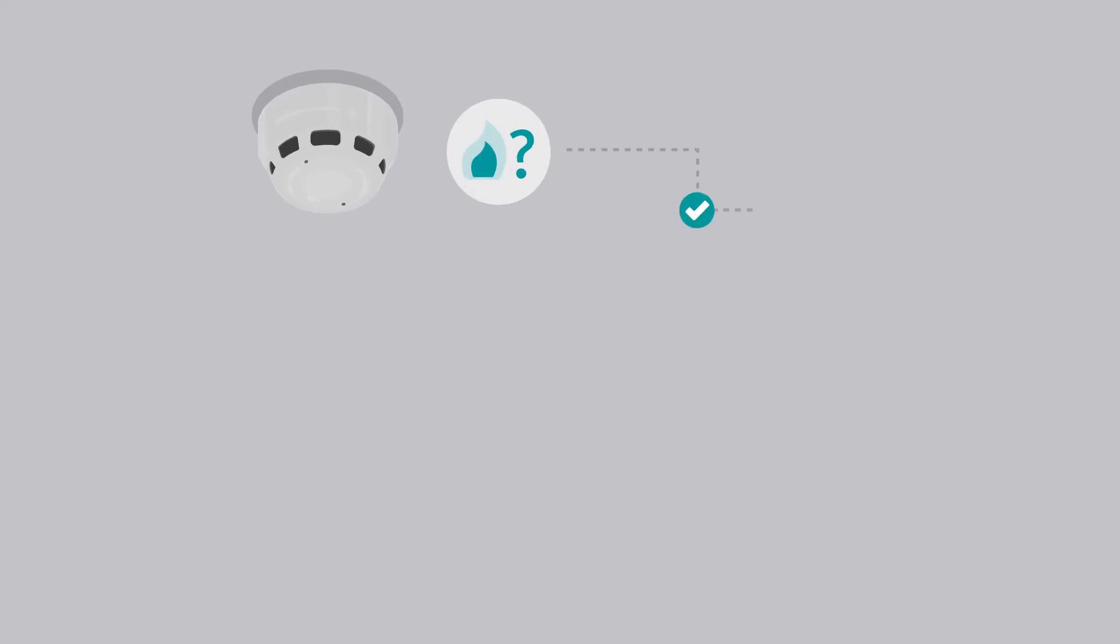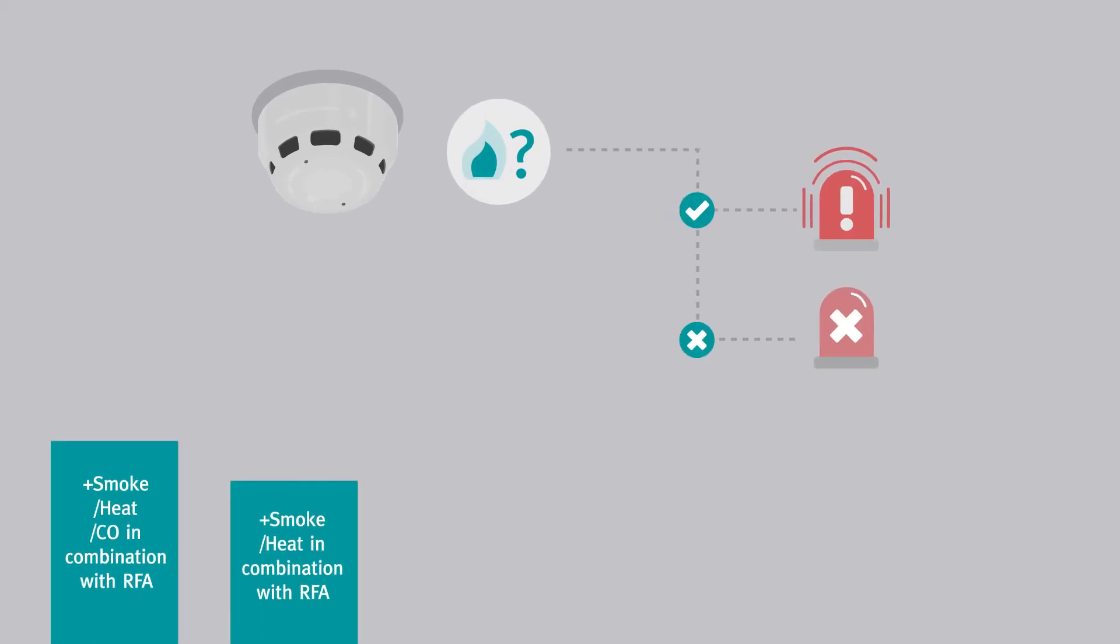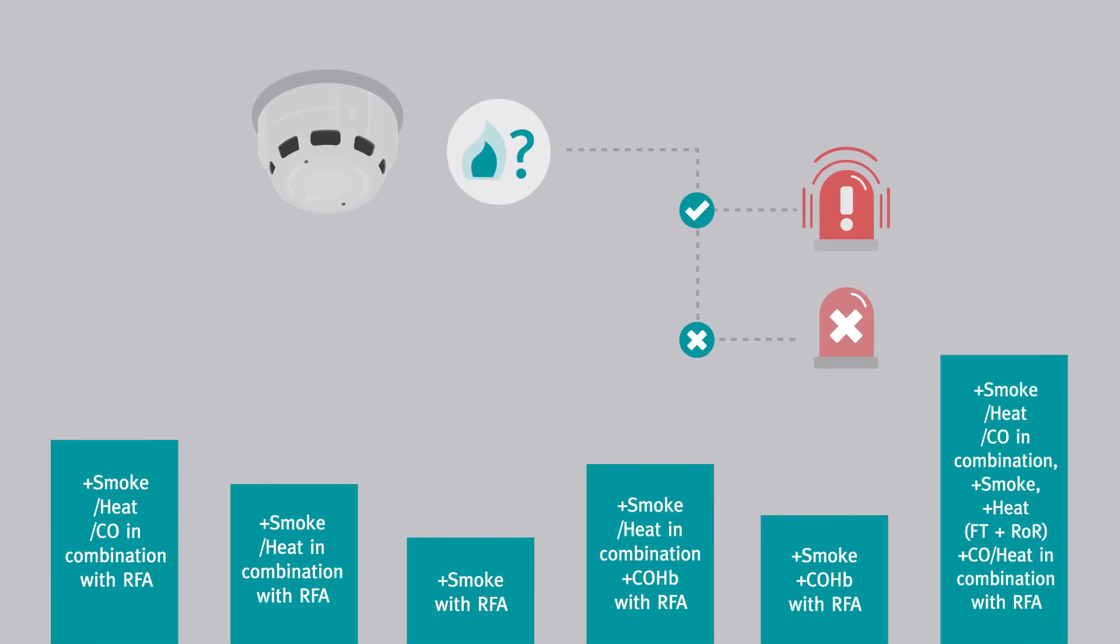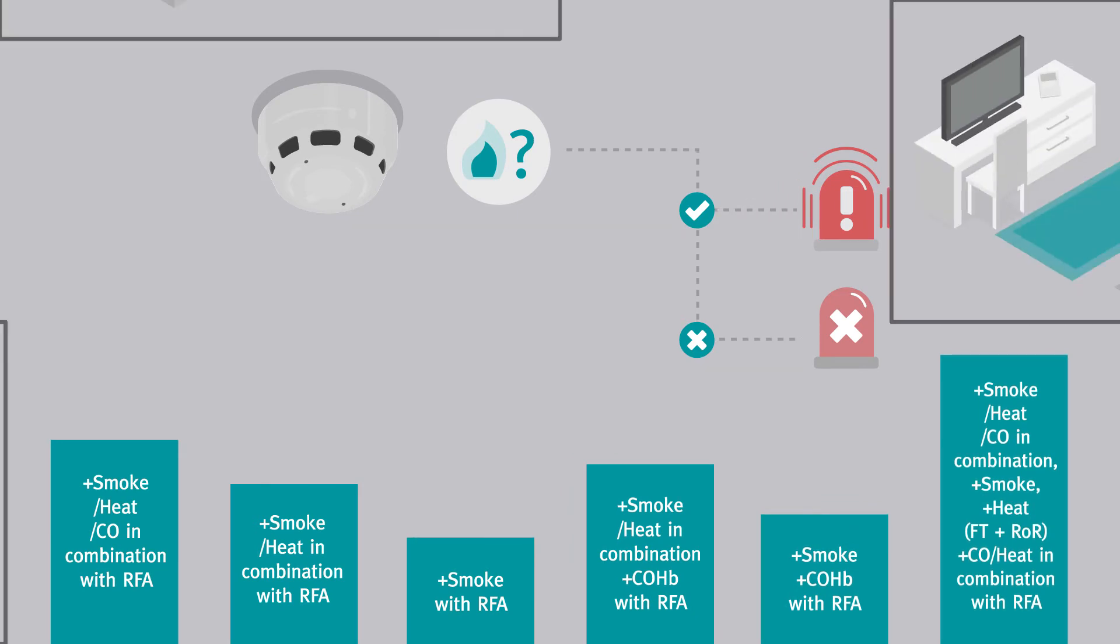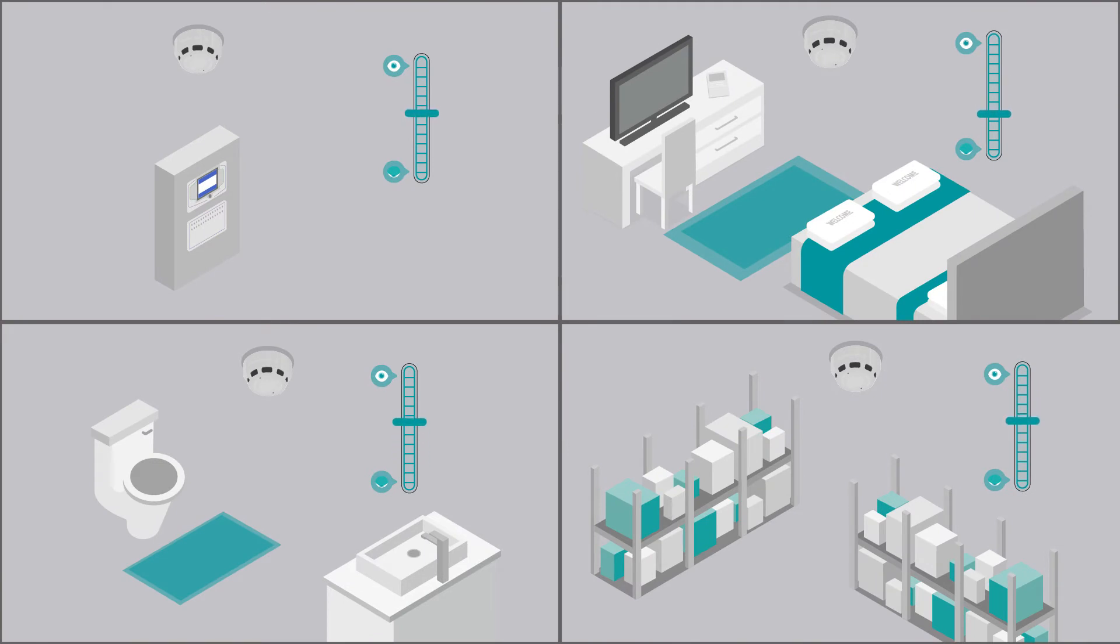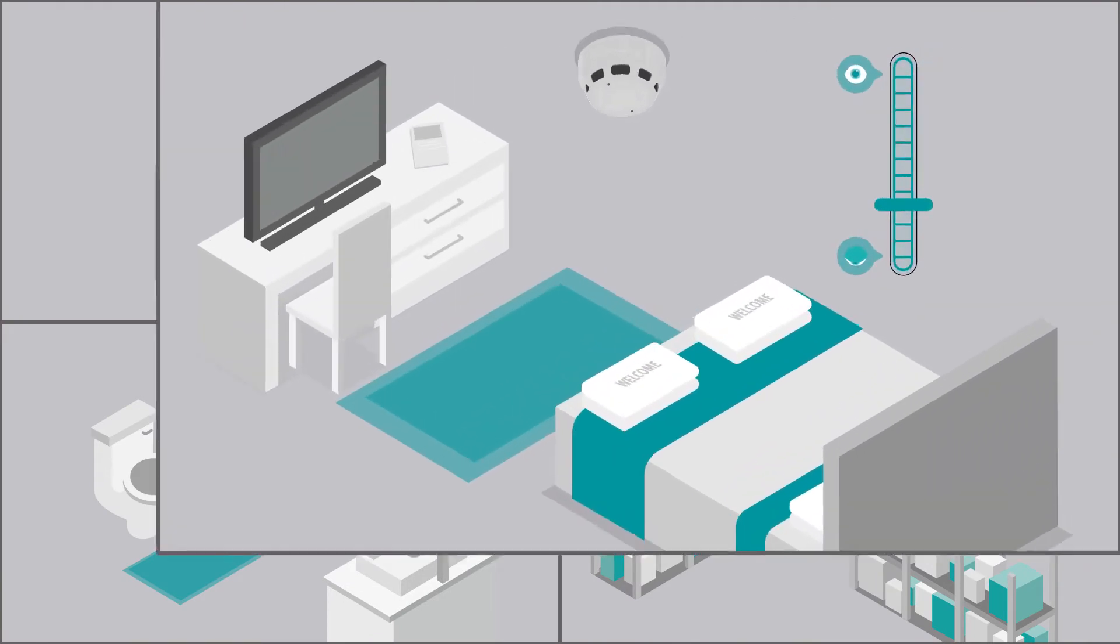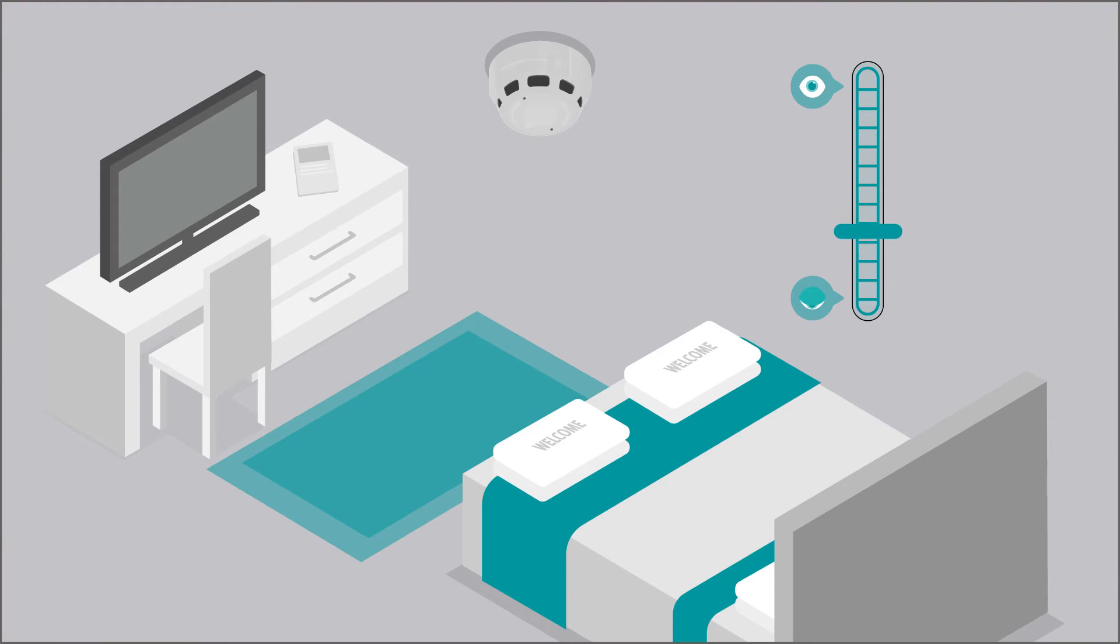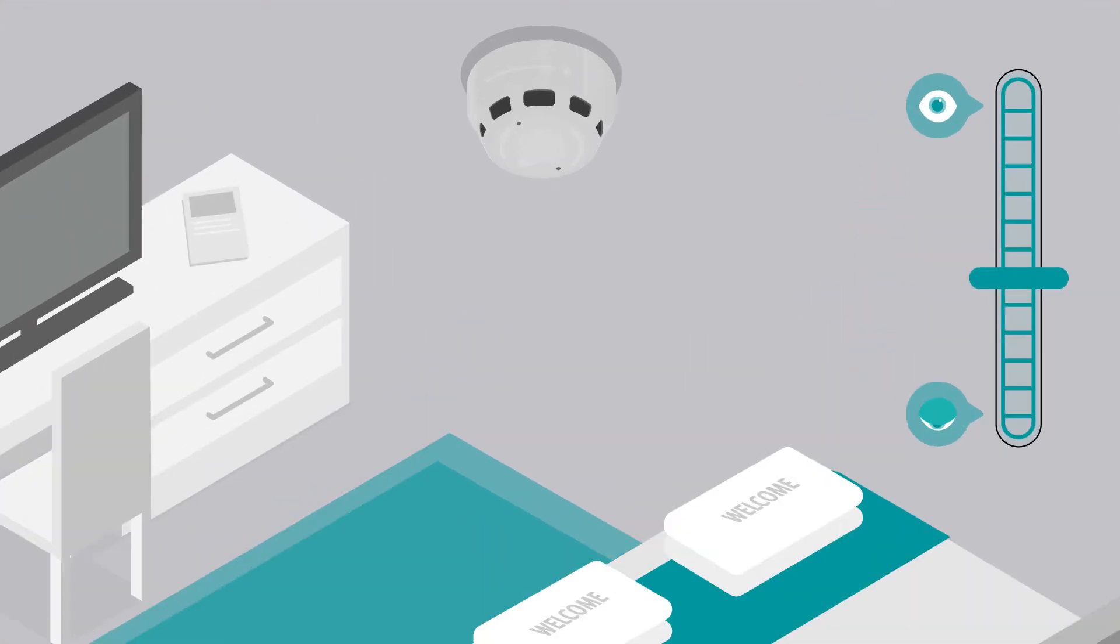The ACD is also enhanced for false alarm reduction. In the modes featuring the reduced false alarm function plus RFA, the sensor will automatically adjust the sensitivity of the optical sensing element over time, learning from its surrounding environment from the moment of installation.